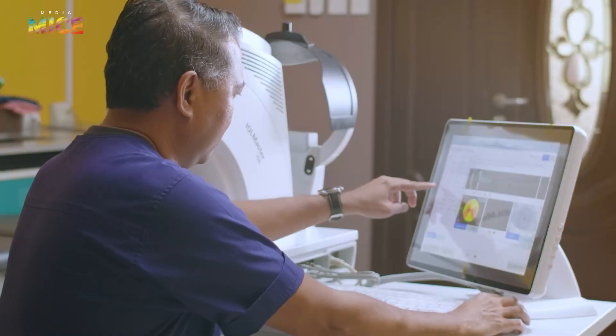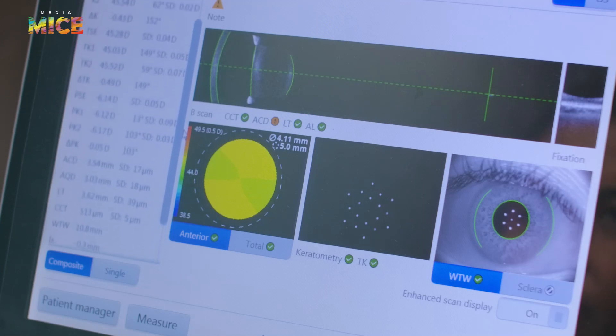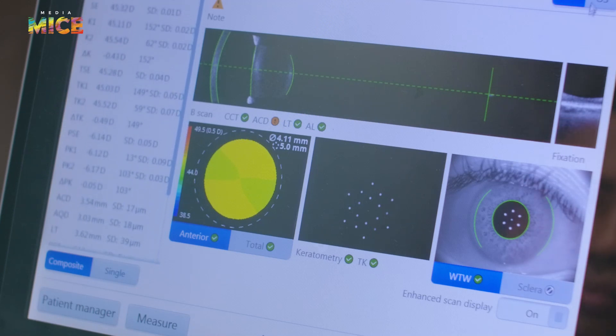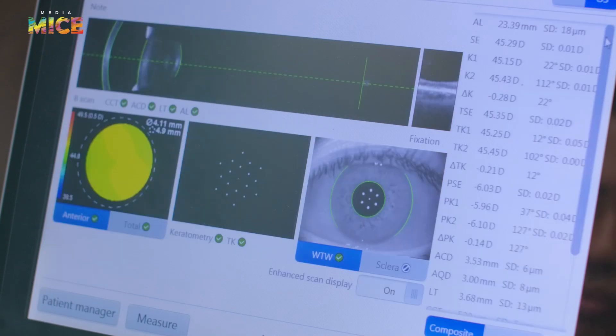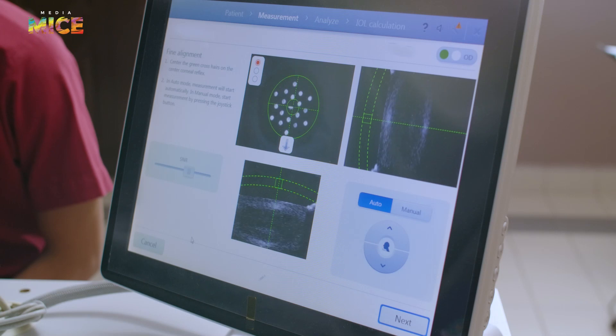Specifically, the IOLMaster 700 from Zeiss, as an example, can be used to measure the following parameters: axial length, anterior chamber depth, keratometry and total keratometry, and white-to-white diameter — also known as horizontal visible iris diameter in the IOLMaster 700. These parameters are very important because they will be used in the calculation of IOL power. The benefits of using optical biometry are that it can be done in one sitting in a relatively short period of time and is less dependent on the technician. The IOLMaster 700 is one of the optical biometers that uses telecentric technology, providing accurate and repeatable keratometry independent of the distance of the eye during measurement.